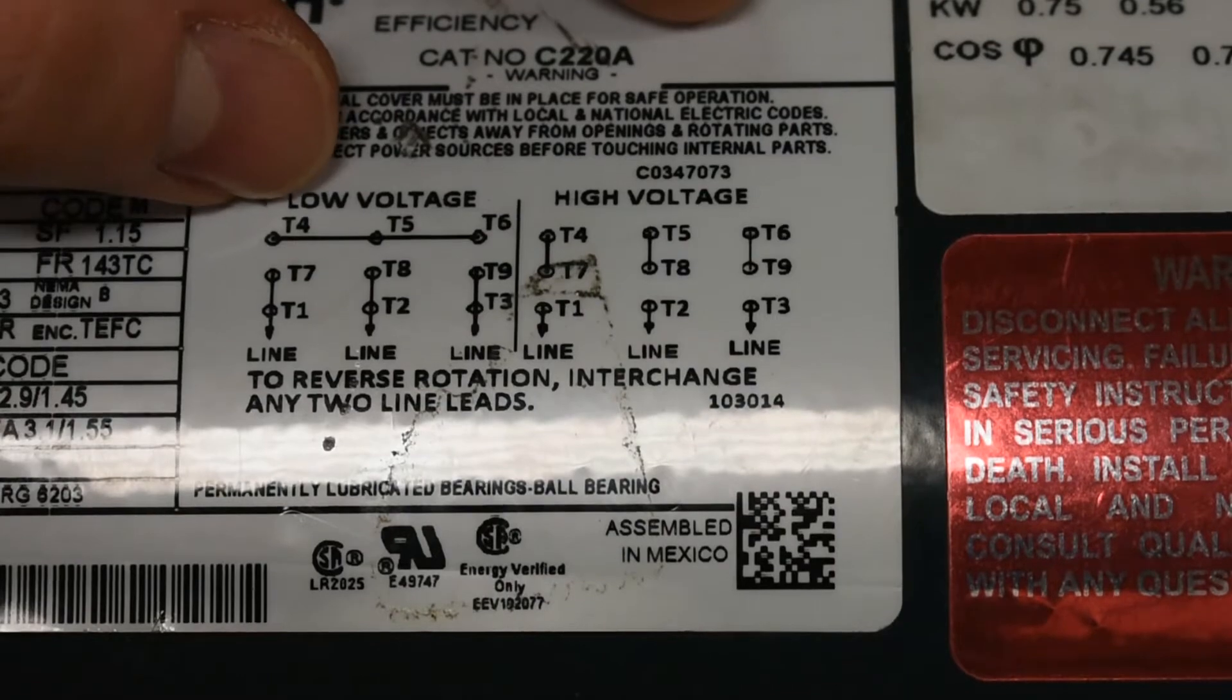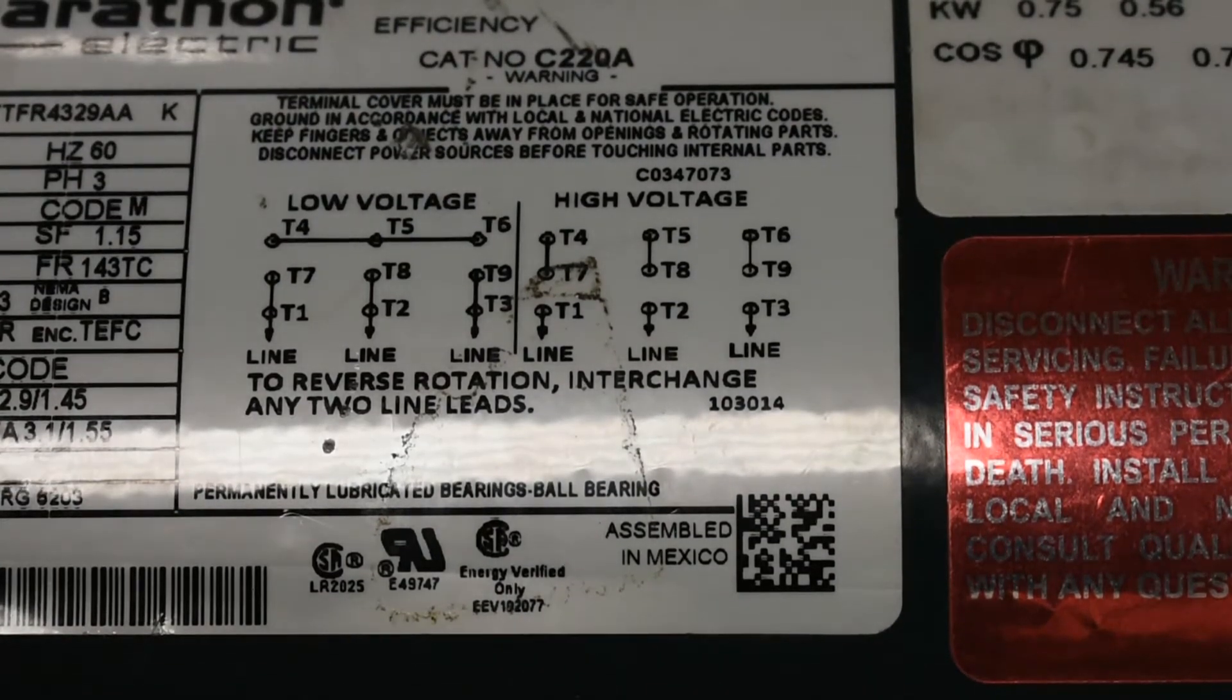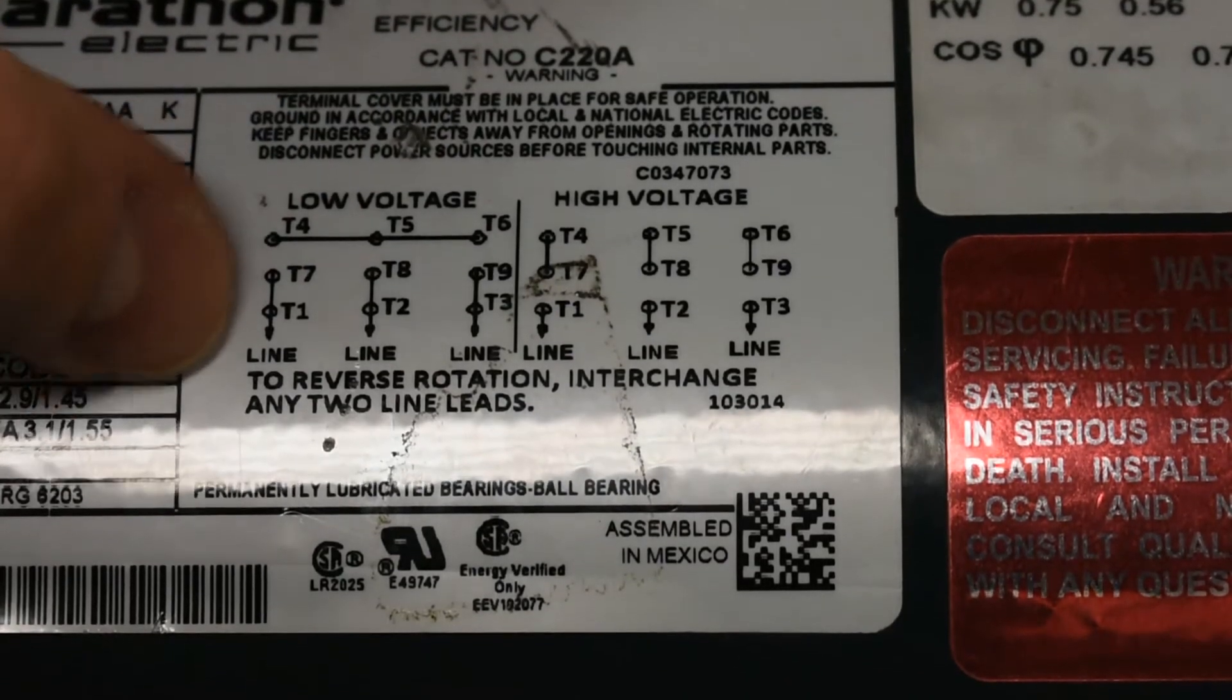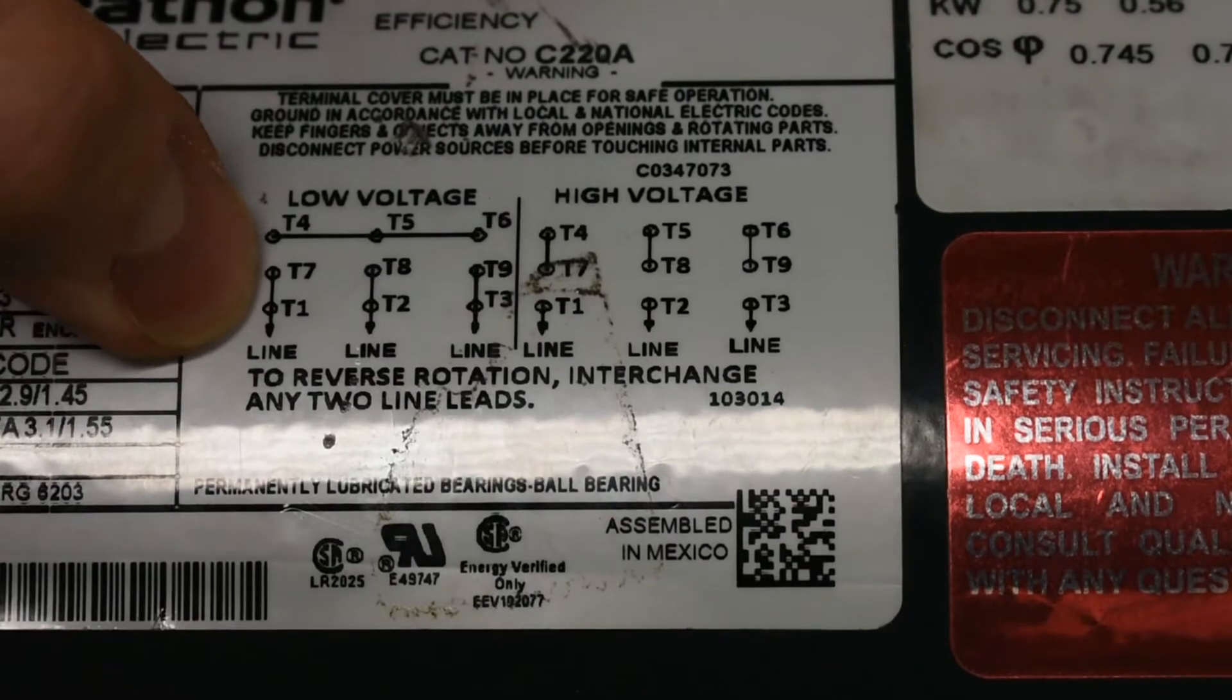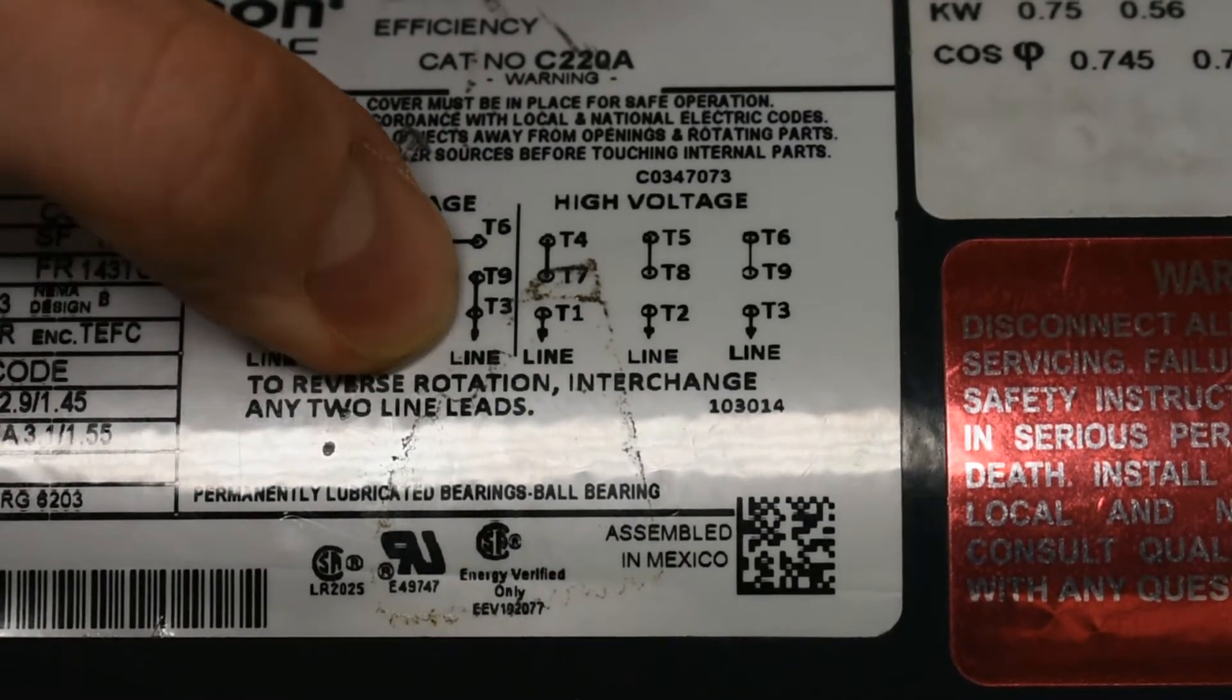Now for low voltage, we're going to connect T4, 5, and 6 together. That's using a wire nut of those nine wires coming out. And then we're also going to use a wire nut that connects a line to T1 and 7, another line to T2 and 8, and a third line to T3 and 9.